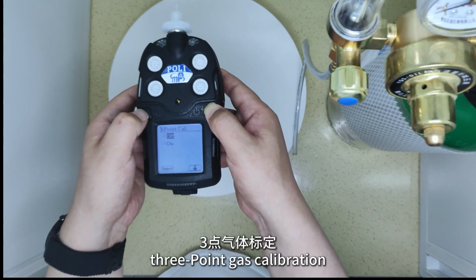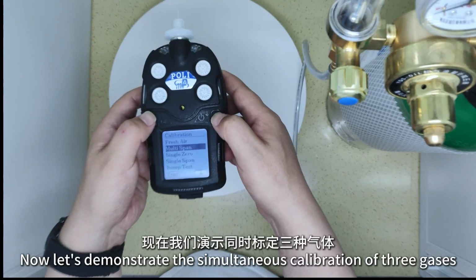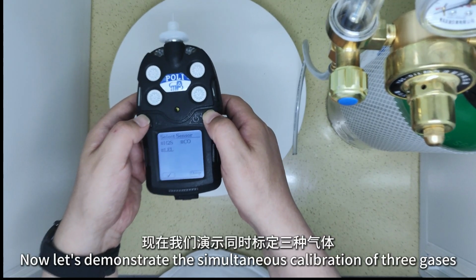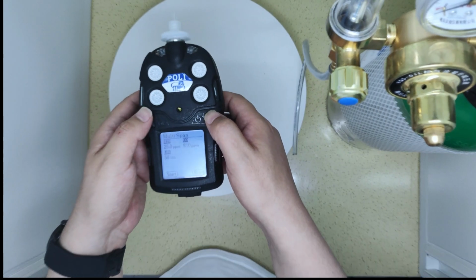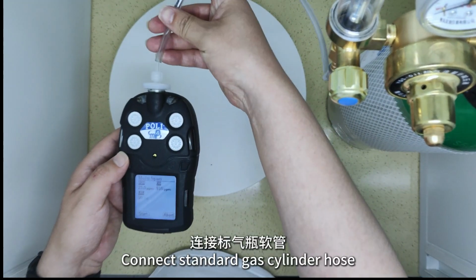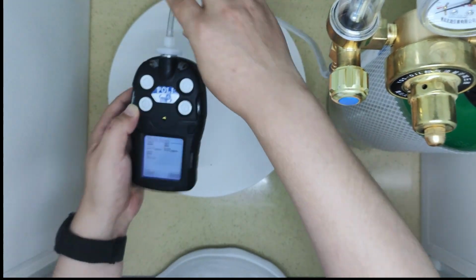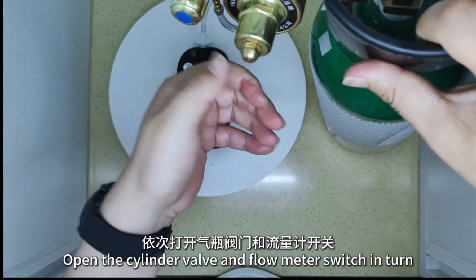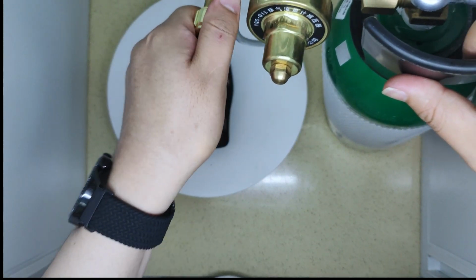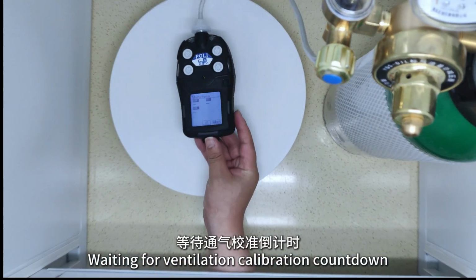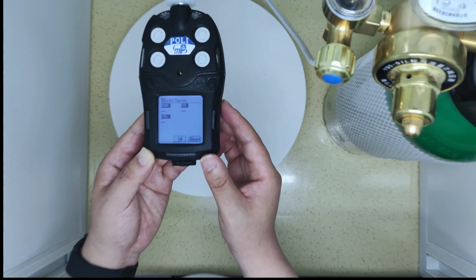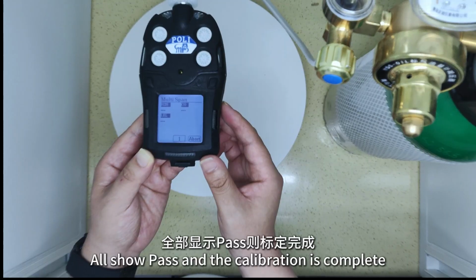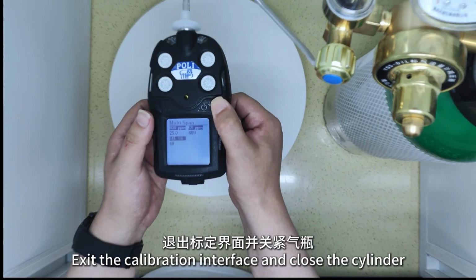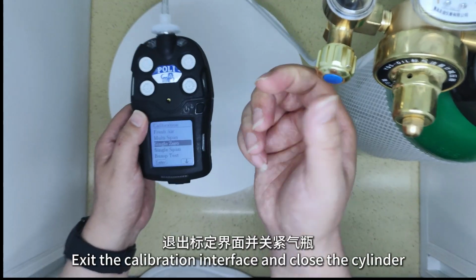Three-point gas calibration. Now, let's demonstrate the simultaneous calibration of 3 gases. Connect the standard gas cylinder hose. Open the cylinder valve and flow meter switch in turn. Wait for ventilation, calibration, countdown. All show pass and the calibration is complete. Exit the calibration interface and close the cylinder.